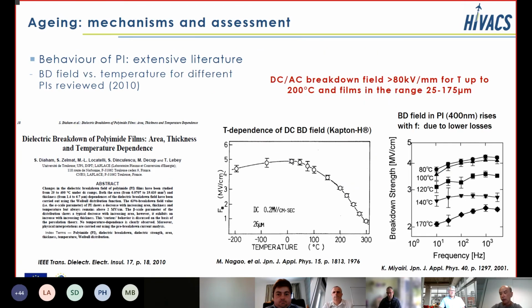Regarding the background on materials, there is extensive literature considering polyimide. For example, there's a review paper here by Diaham on the breakdown aspects of polyimide. What we know from the literature, as we were especially interested in high temperature withstanding, is that whichever the conditions used, there was no breakdown field under 80 kilovolt per millimeter for temperatures up to 200 degrees. There's an example here of breakdown field as a function of temperature, where we are beyond 200 kilovolt per millimeter up to 200 degrees. And if we consider the frequency, which is an important aspect for the project, there is no special degradation of the breakdown field with increasing frequency, and even an increase of the field apparently, that could be due to perhaps having fewer losses when increasing frequency.